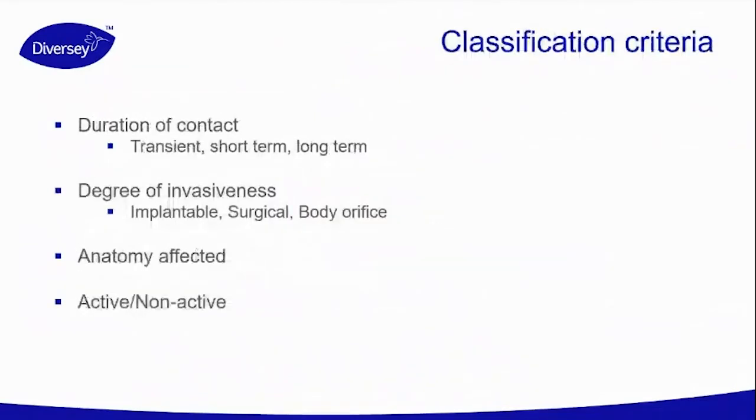The classification criteria, so it's the duration of the contact of the medical device with humans, either transient, short-term, or long-term, the degree of invasiveness of the medical device, implantable, surgical, body orifice, the anatomy affected by the medical device, and whether the medical device is active or non-active.